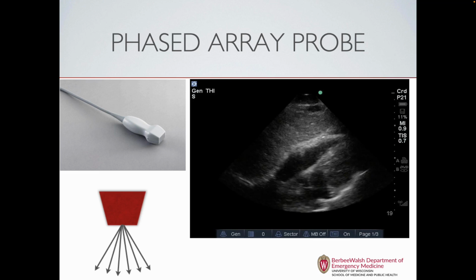It's got a poor near field resolution because the beam is diverging out, but it gets better about midway down. And its frequency is about 5 megahertz, and the depth for this one is about 21 centimeters. Most commonly, we'll use this one for cardiac ultrasound, but we can do it for some abdominal scans and chest scans as well.